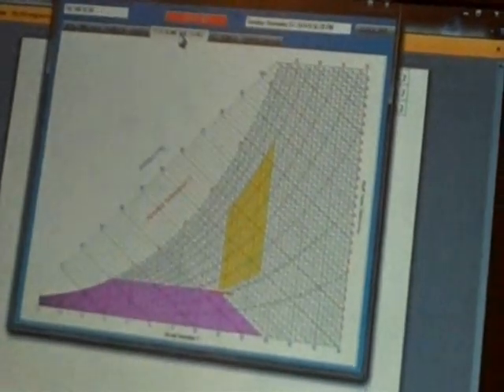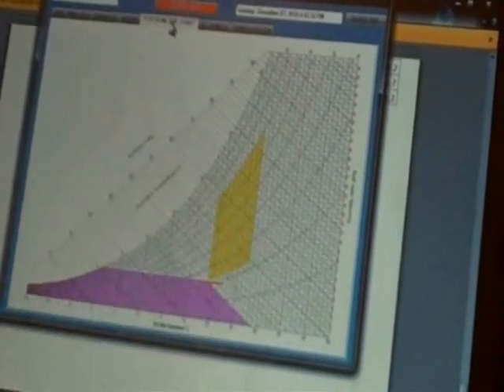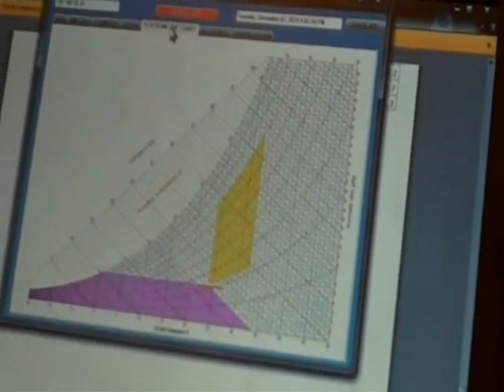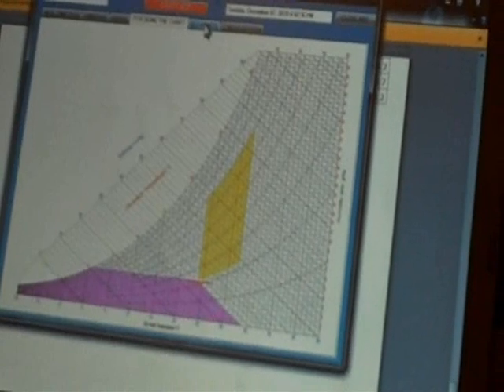A psychrometric chart helps those really technical guys see where the system is running within those boundaries. And again, we can go into that in great detail. Then here are the set points. So I mentioned before that we can actually set temperature and humidity for the system to react to. And what I'm going to do right now is straightforward. Take it from 15% fan speed up to 100, and you'll hear the system speed up. And so while that's doing that, I'll just open the door.